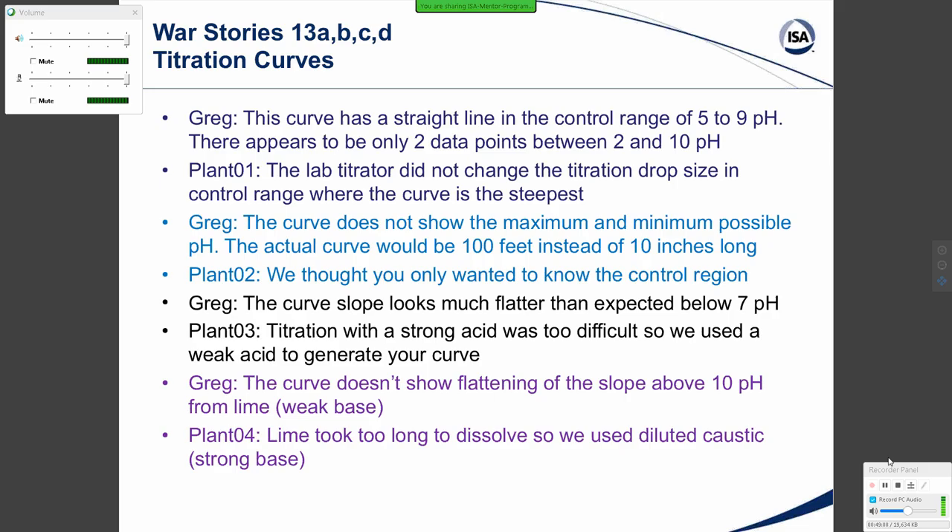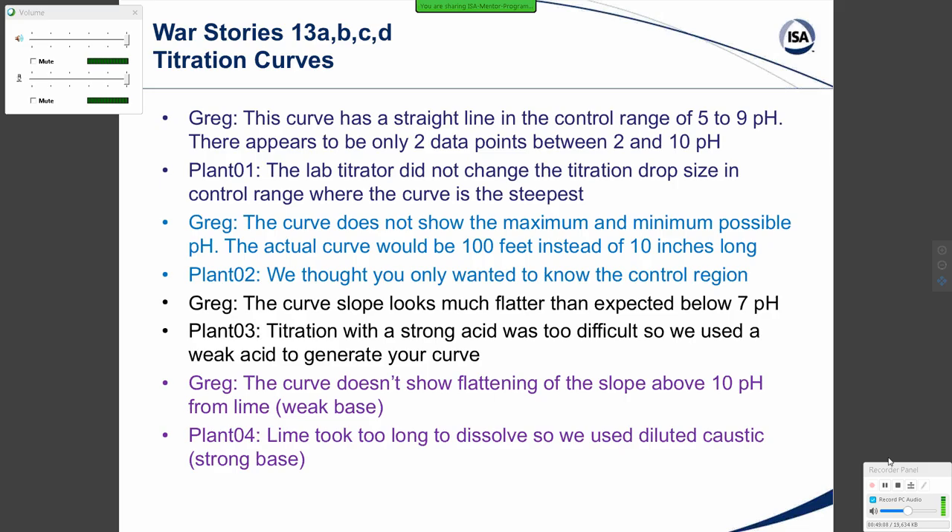In yet another application, the titration curve didn't show flattening in the slope above 10 pH from lime — a weak base — because the lime took too long to dissolve, so they substituted a little caustic, a strong base, which produces a completely different curve.